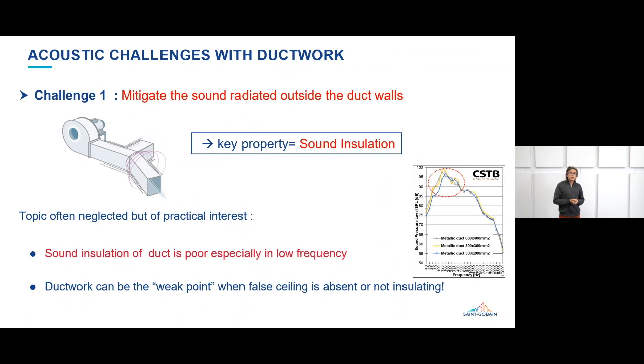So the first acoustic challenge we have to address with a ductwork system is to be able to mitigate the sound radiated outside the duct walls. The key property, the key rating to address this issue, is the sound insulation criteria. From our experience, this is a topic quite often neglected in practice, but yet it is quite relevant. Why? Because the first point is that the sound insulation of a ductwork is generally quite poor, especially in low frequency.